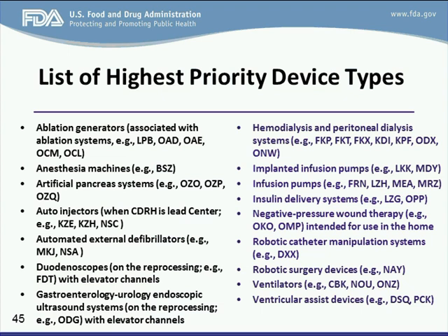So in the event that you have a product that is a combination product that includes, let's say, a drug delivery system, such as a pen injector or a jet injector or things like that, the lead centers for those submissions are either CDER or CBER, depending upon whether you're talking about a biologic or a drug. And those submissions aren't governed by this particular guidance document.